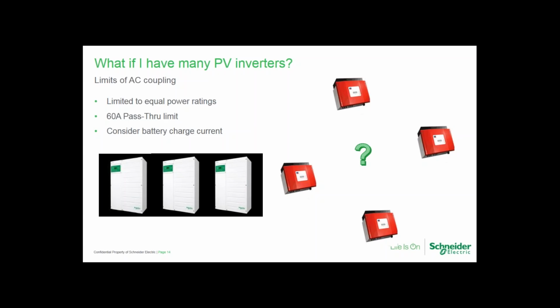So as far as scalability goes, when you're AC coupling, it's important that PV power does not exceed the XW system continuous power rating. For example, if you have 3 XWs, that would give you, say, 18 kW continuous at 40C, or 20 kW at 25C, and you have less than 20 kW of PV inverters, then that's acceptable.